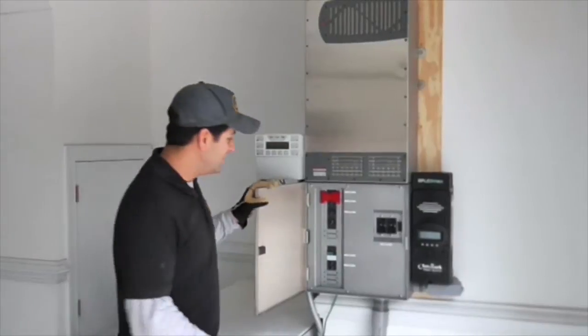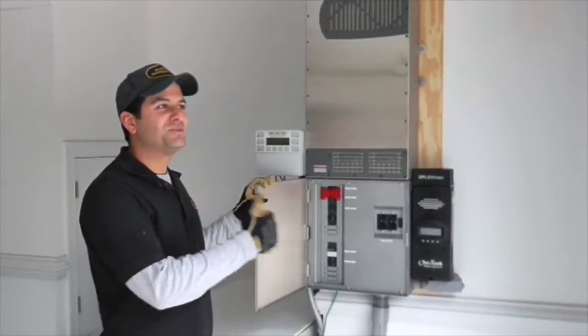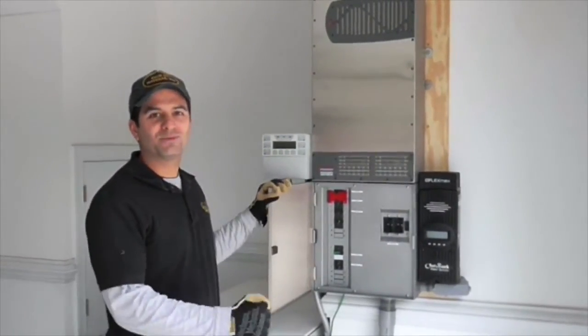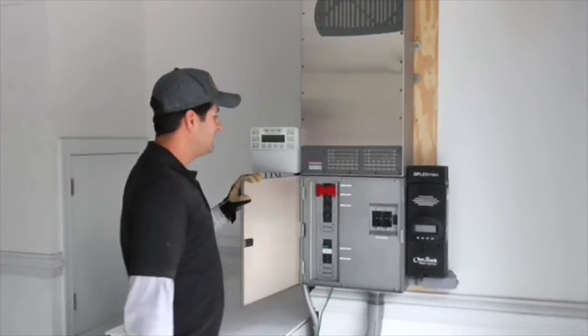Some of the disadvantages is that it's really tough to get certain breakers in here and certain wires attached. The battery cables are very difficult to get installed in here. I've actually read about this online, but when we did it, you realize yeah, it was pretty tough. Getting the battery cables installed was difficult.